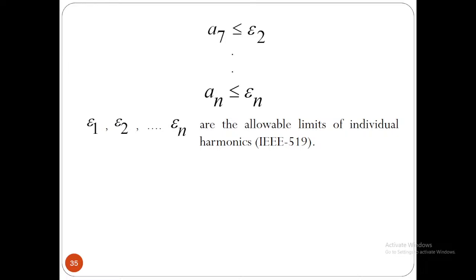Whenever you are feeding power to a particular grid, at the point of common coupling, PCC, probably you have heard that term, point of common coupling. At that point, your individual harmonics should not exceed a specified value and the THD should not exceed a particular value. That is the limit set by the IEEE. So that is dependent upon your system voltage, right? So for different system voltages, the specification is different. So if you have a 69 kV system as per IEEE 519, the individual harmonics should not exceed 3%. That is the international standard. Individual harmonics should not exceed 3% and the total harmonic distortion THD should not be more than 5%. Right? So that is 519.